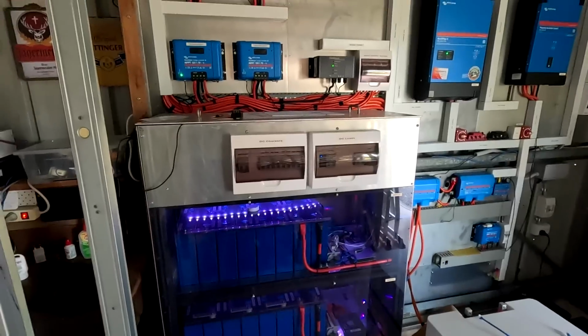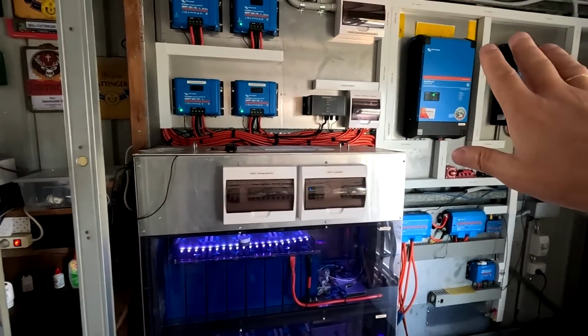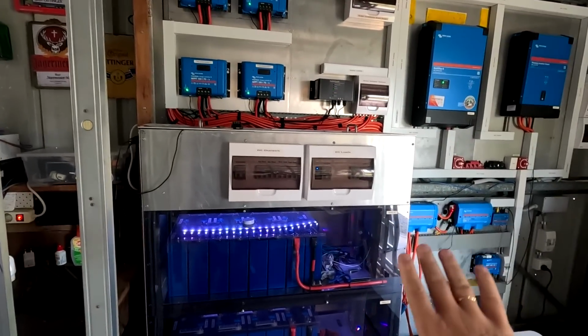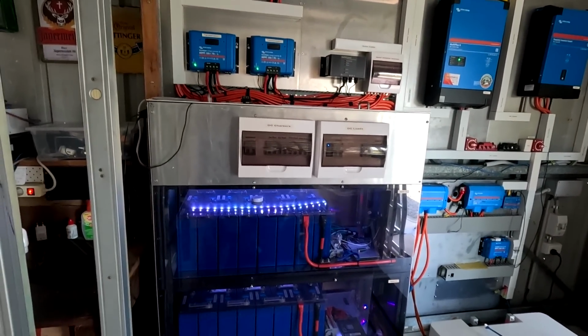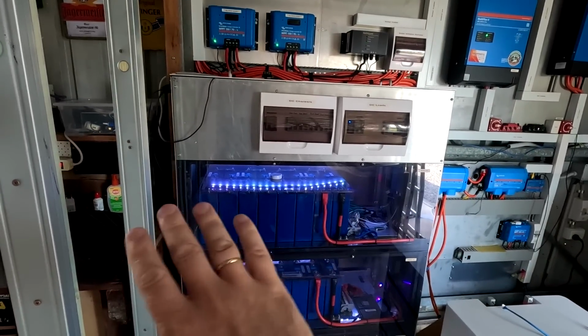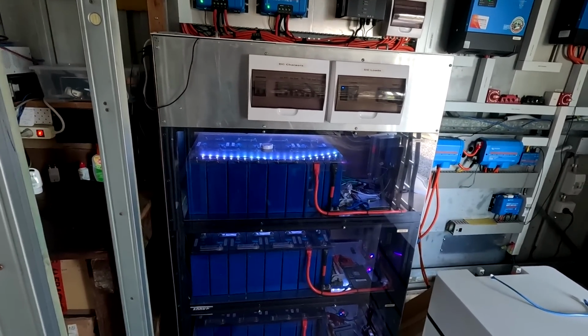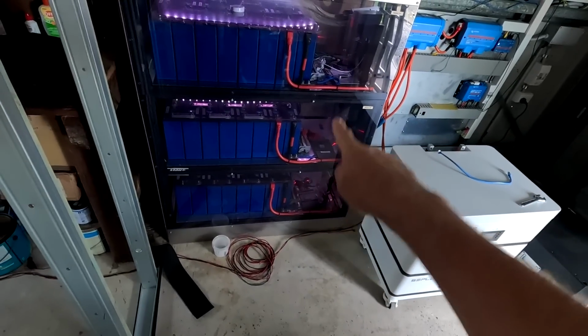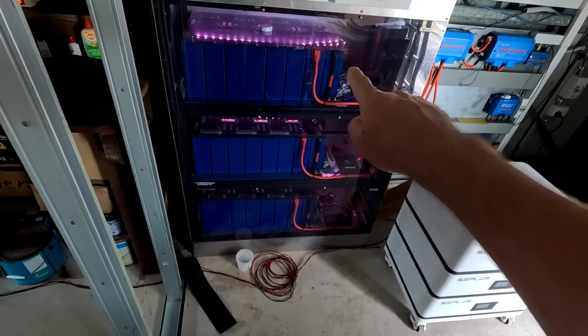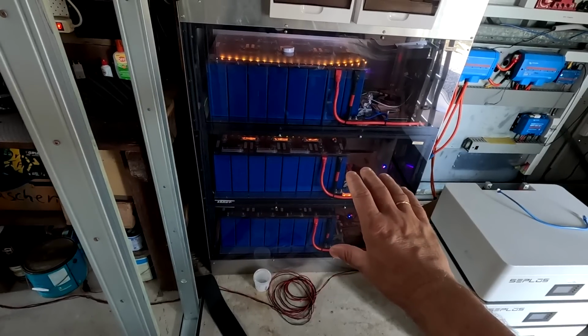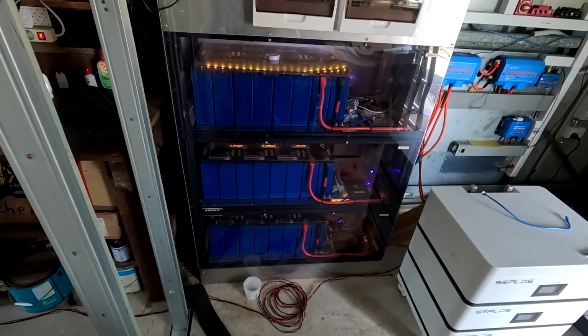So do you need communication? Absolutely not. If you set up all your solar charge controllers and inverters correctly, no communication is necessary. Voltage is totally fine to charge these lithium iron phosphate batteries with, and each of the BMSs takes care of one battery bank. If one turns off, the other two are still online and keep your system alive and running. Obviously, without communication, you don't know that one of your batteries has turned off.